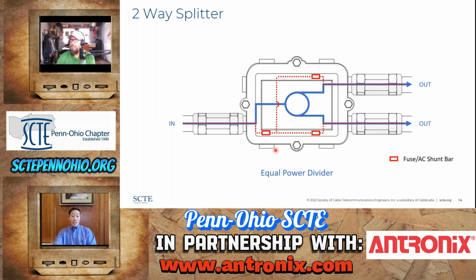You can actually activate or deactivate AC going down each of the ports independently. So there's a fuse or an AC shunt bar on each of these ports. Line passives are typically shipped with these AC fuses pre-installed, but based on network design, if you remove one, you can save power if there are no active devices going out, let's say, this leg. Then you can remove the fuse from this location and there's no AC going down that leg. So they're configurable where AC can go down all or none of the ports.